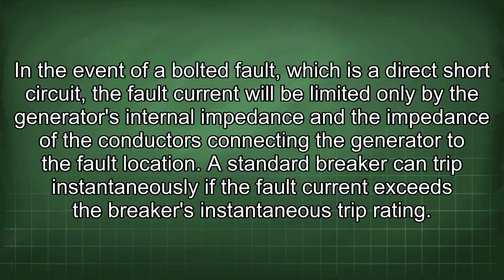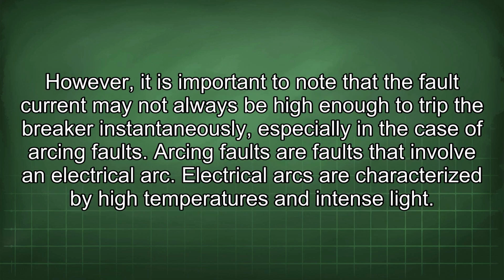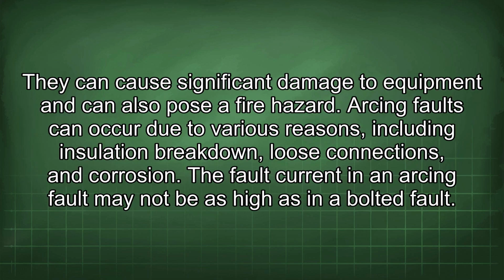A standard breaker can trip instantaneously if the fault current exceeds the breaker's instantaneous trip rating. However, it is important to note that the fault current may not always be high enough to trip the breaker instantaneously, especially in the case of arcing faults. Arcing faults are faults that involve an electrical arc. Electrical arcs are characterized by high temperatures and intense light. They can cause significant damage to equipment and can also pose a fire hazard.